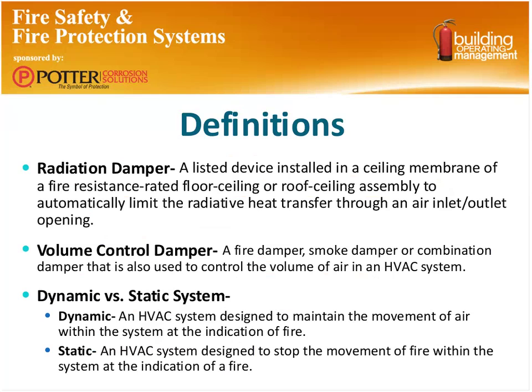And then there's a term we need to understand, and that's dynamic versus a static system. A dynamic system is one where we're maintaining the movement of air within a system, and we're going to keep that air moving, but we're going to control it. A static system is really meant to stop the flow of air in the event of a fire.